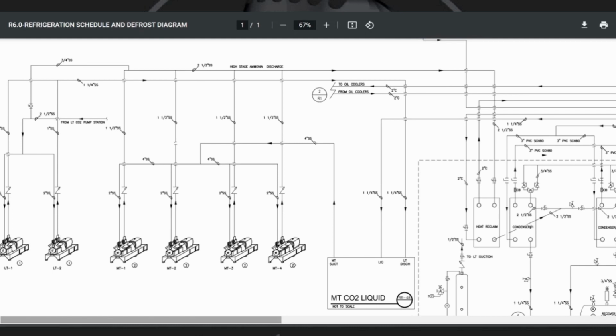Yeah, without it, you're just wasting money. All you're doing is venting CO2 the entire time, especially with the 3,000 pound charge on a medium temp. That's quite a hefty bill to vent out there. So a single unit as an auxiliary, you almost have to have it with something that big.